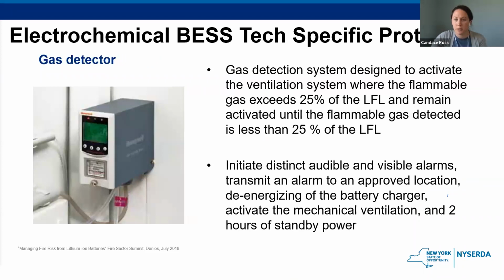And also, as part of the exhaust ventilation requirement, a gas detection system is required to monitor the levels of gas in the unit. This will trigger appropriate ventilation and inform operators of unusual levels of off-gassing. So any failure of the gas detection system will also trigger a trouble signal.